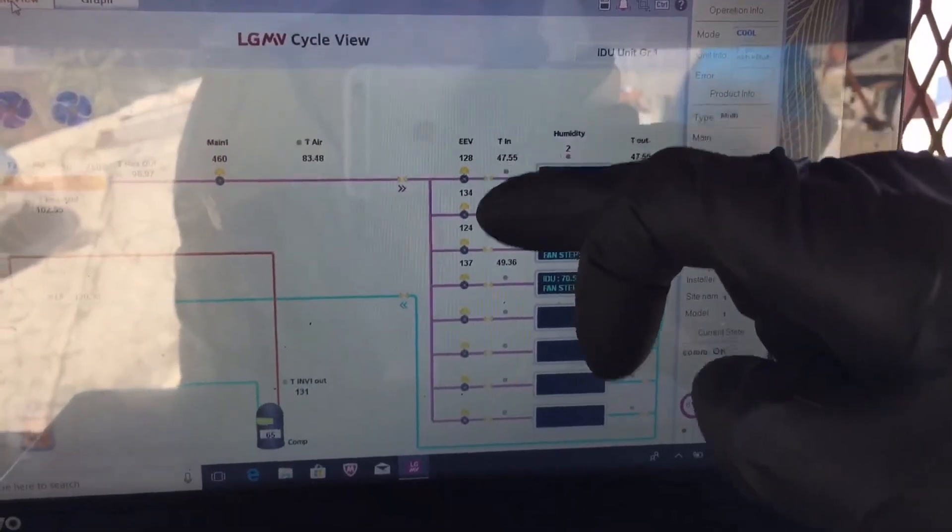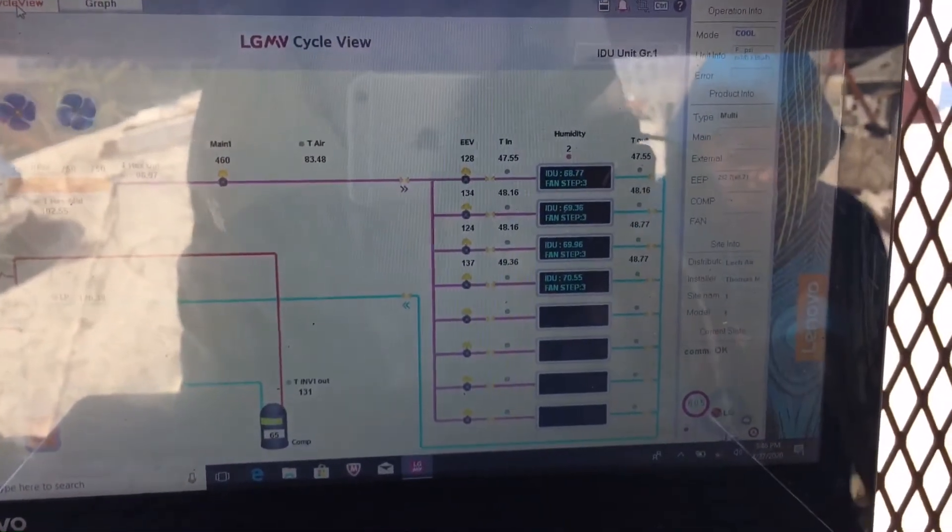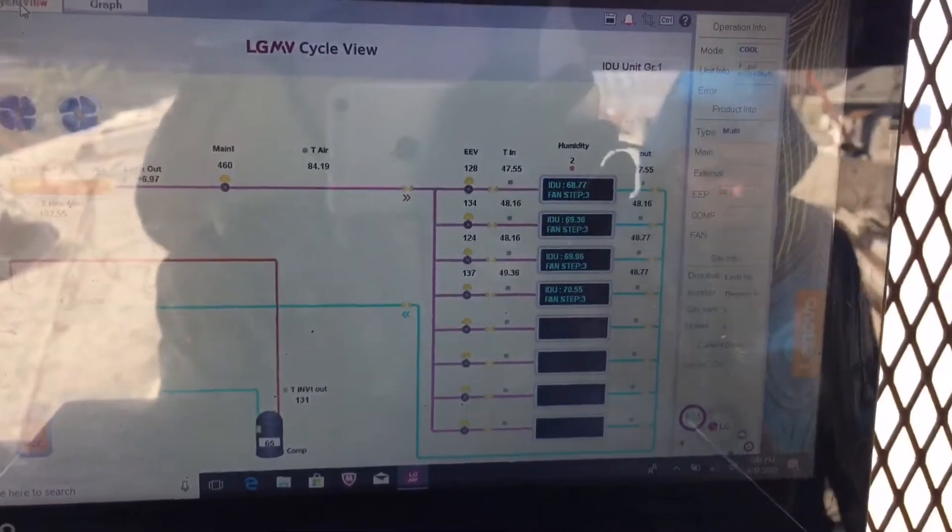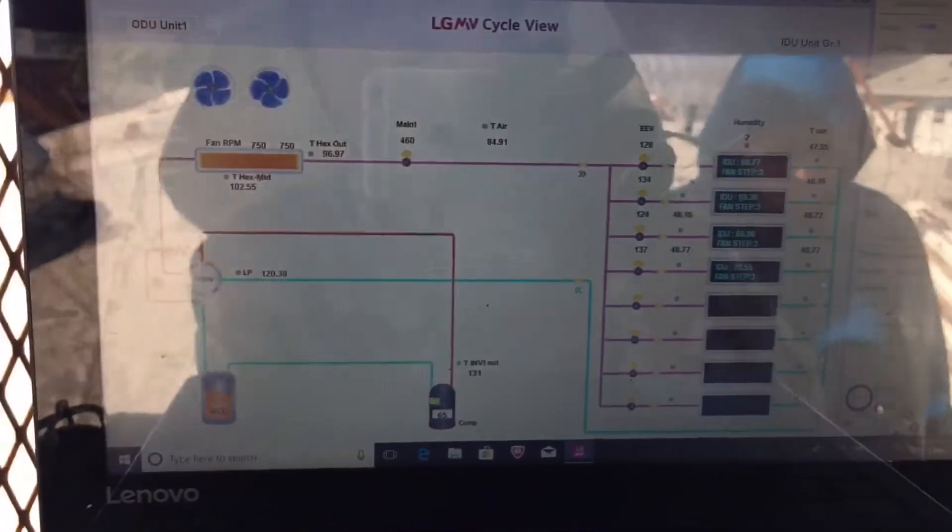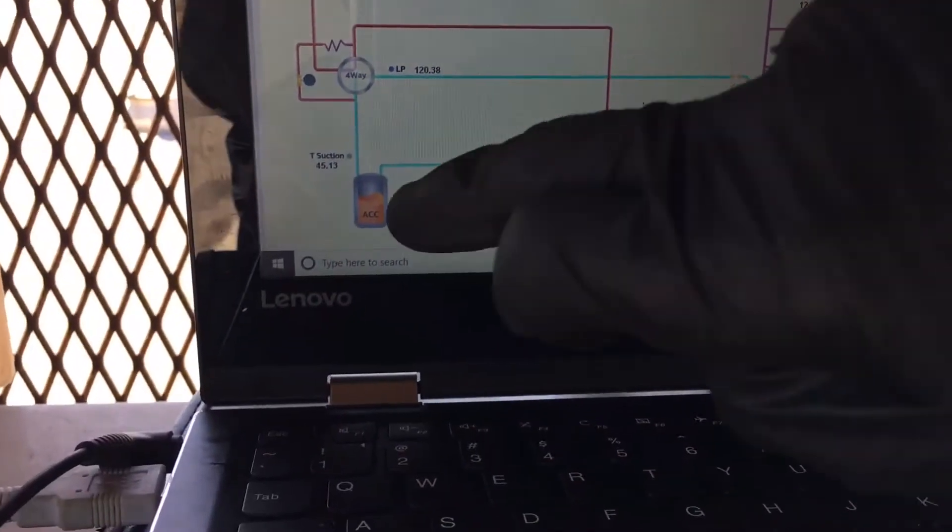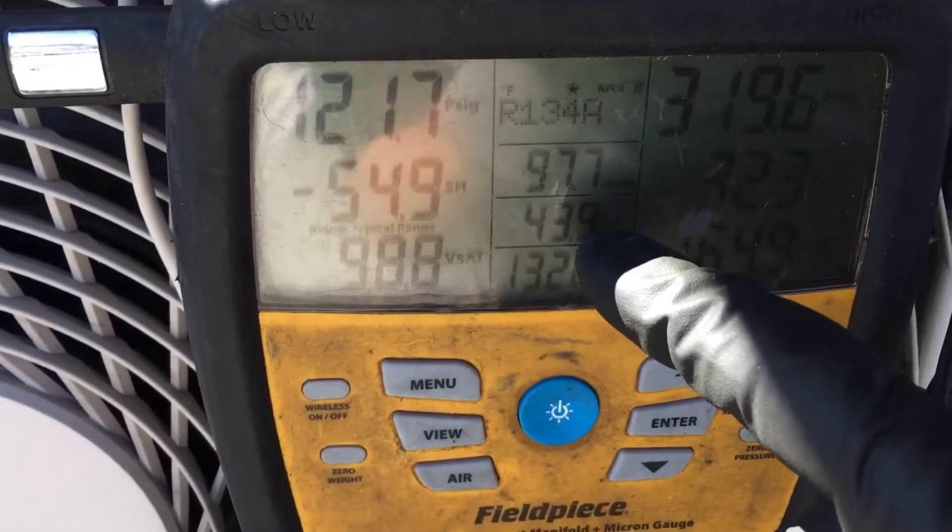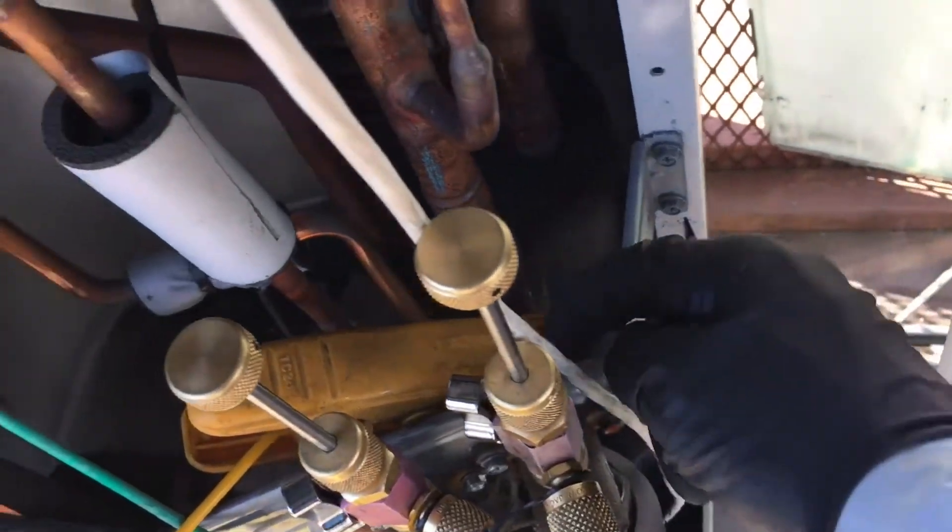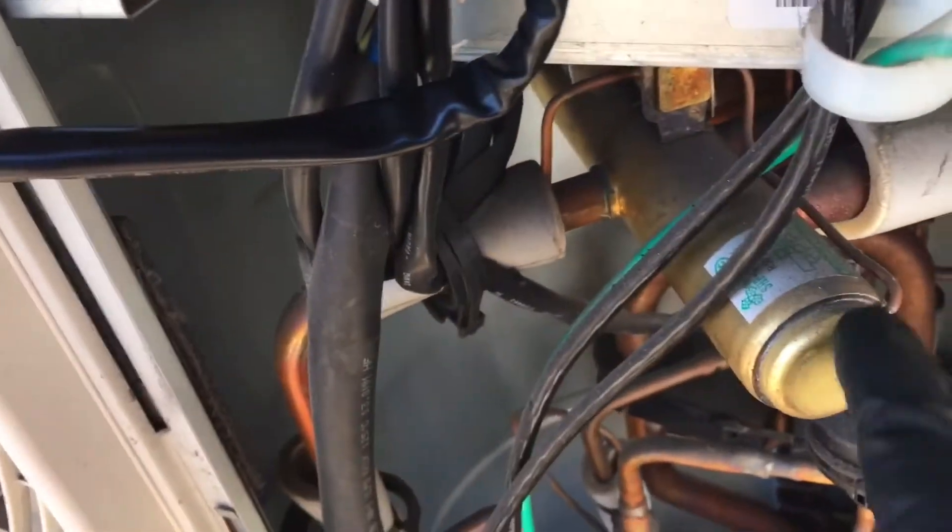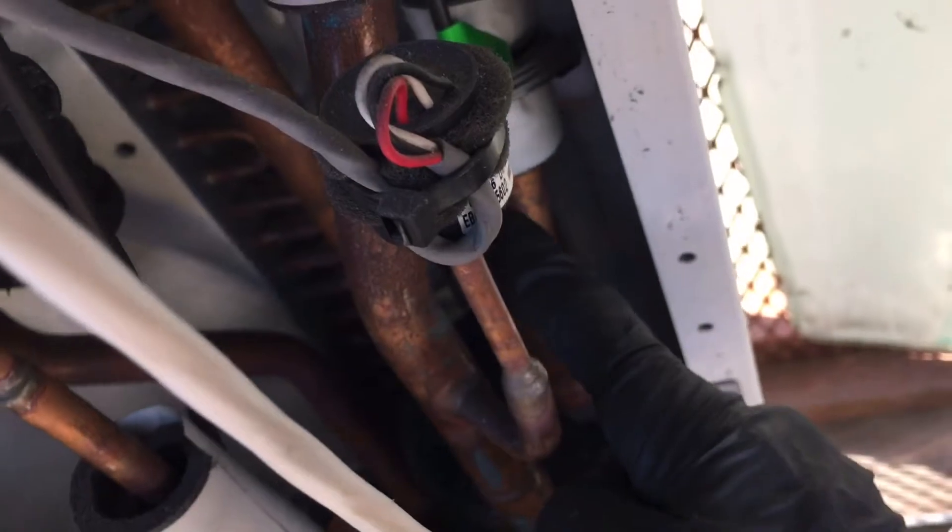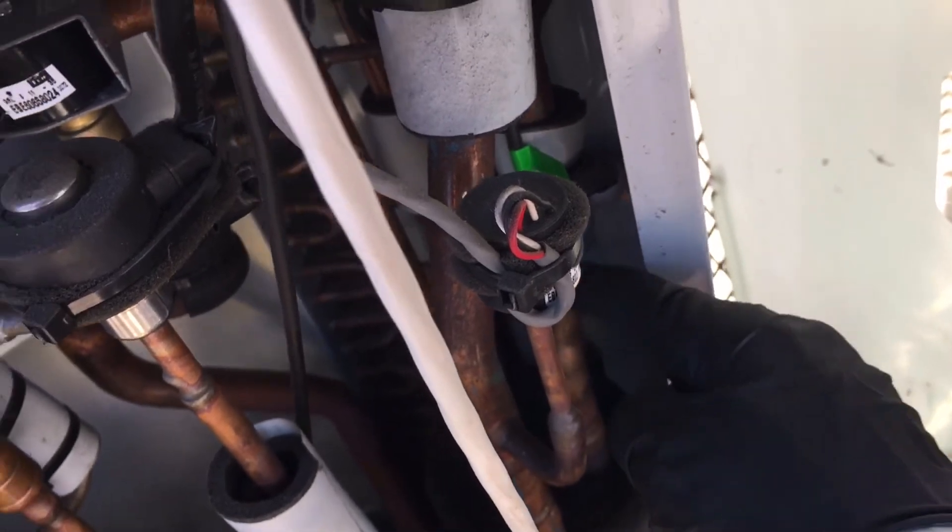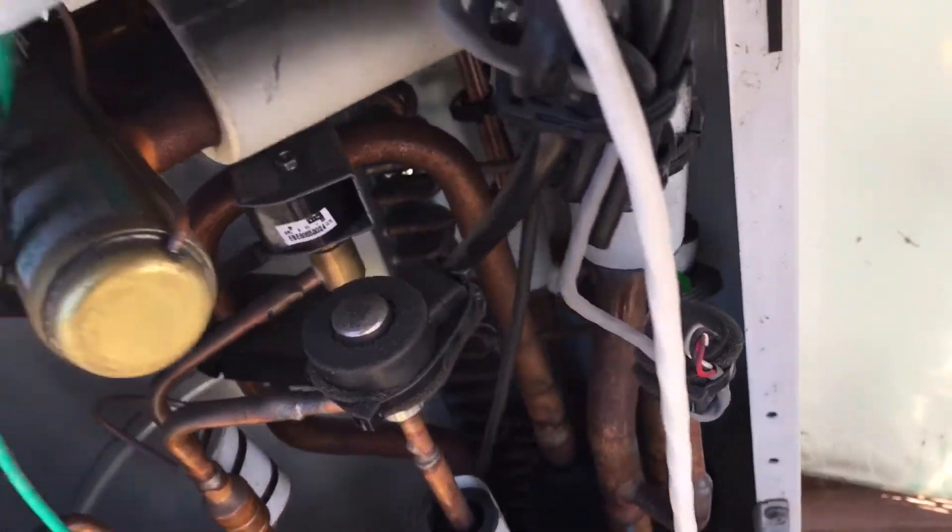So here we're back at our expansion valves on our heads. Here's our heads and there's our temperatures in and out. There's our suction accumulator temperature right there, 45 degrees. And I'm close, my clamp is right here coming out of there, so I'm at 43 degrees. The reason I'm at 43 degrees is because you see this is insulated, then we're coming exposed. My temperature clamp is right there. Their temperature pickup goes up here to your reversing valve, then goes back out, comes down. Their temperature probe is right here, so I'm before, and that's why I'm picking up a few degrees cooler than what they're picking up. This is where they want to measure temperature at.